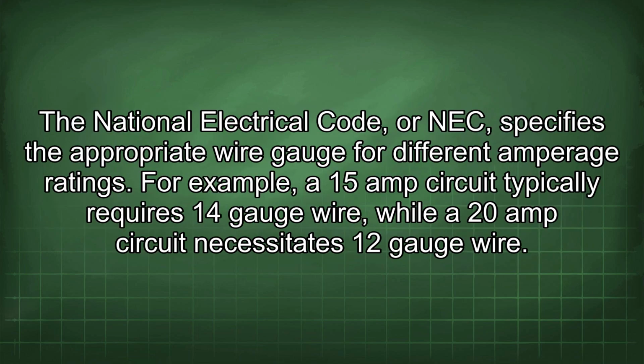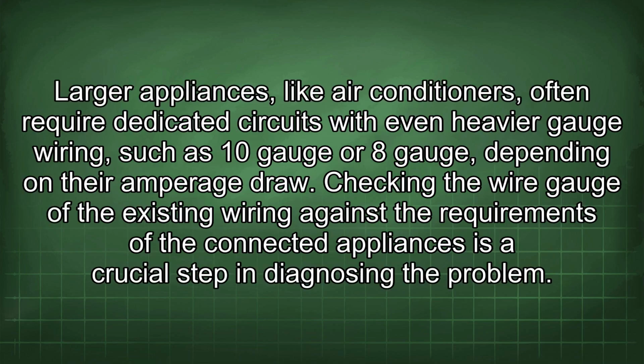The National Electrical Code, or NEC, specifies the appropriate wire gauge for different amperage ratings. For example, a 15 amp circuit typically requires 14 gauge wire, while a 20 amp circuit necessitates 12 gauge wire. Larger appliances, like air conditioners, often require dedicated circuits with even heavier gauge wiring, such as 10 gauge or 8 gauge, depending on their amperage draw.